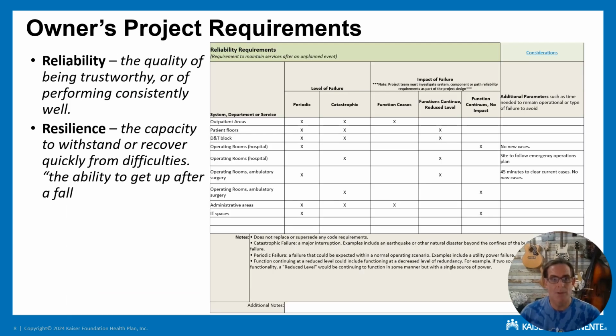And then we get to reliability, being trustworthy and performing consistently, and resilience, which is the capacity to withstand or recover from difficulties. For outpatient administrative areas, if there is a periodic or a catastrophic failure, the functions of those areas simply stop. If we were to have a 4-hour power outage at a medical office building, we would not continue to provide services. It shuts down, as simple as that. The majority of our hospital services, the patient floors, the D&T block, in the case of a periodic or a major failure, we would continue to operate, but we'll be operating at reduced capacity. That reduced capacity is a very key concept.